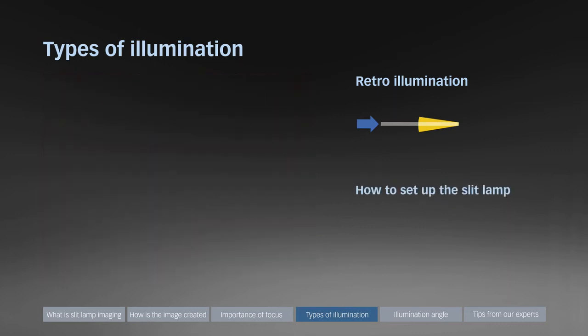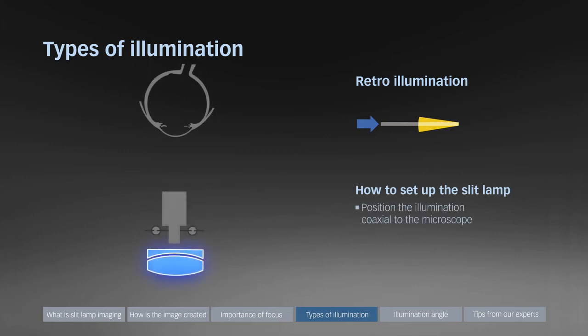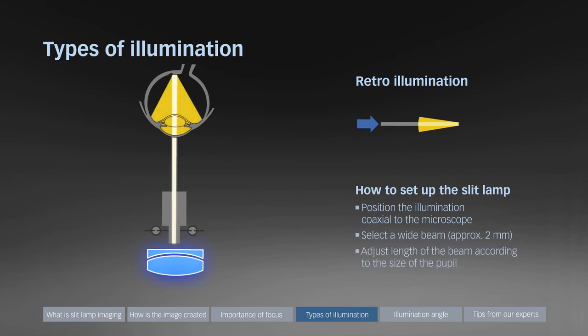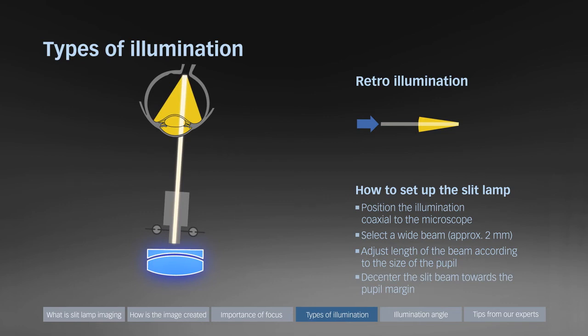To set up the slit lamp for retro illumination, position the illumination tower coaxial to the microscope, select a moderate beam width of between 1 and 2 mm, adjust the length of the beam according to the size of the pupil. De-centering the slit beam towards the pupil margin optimizes the illumination and removes unwanted reflections from the center of the image.